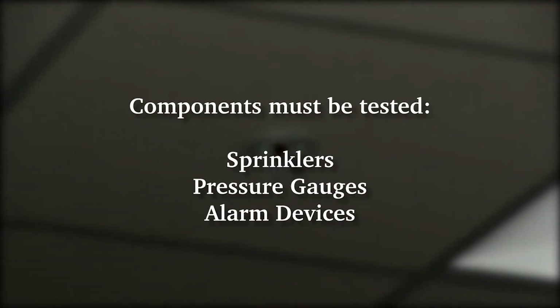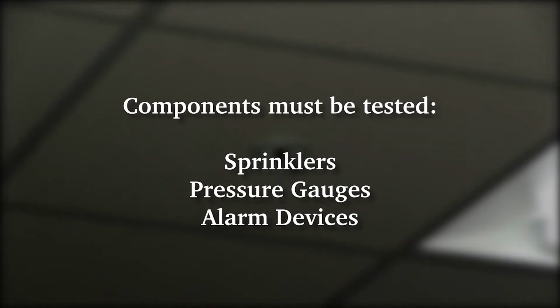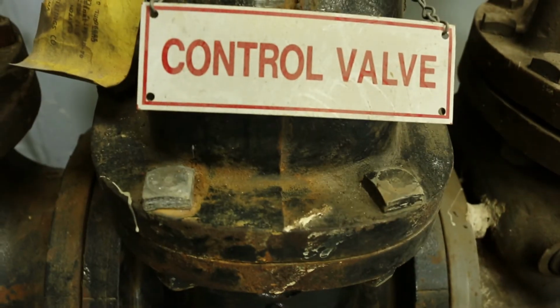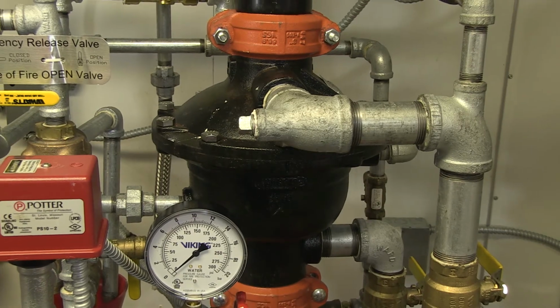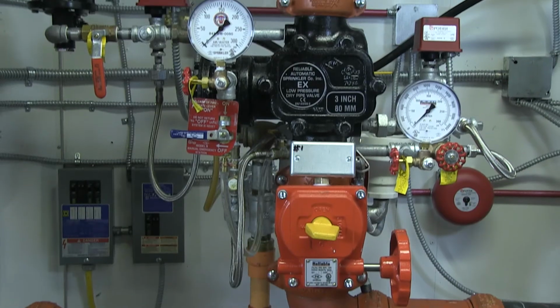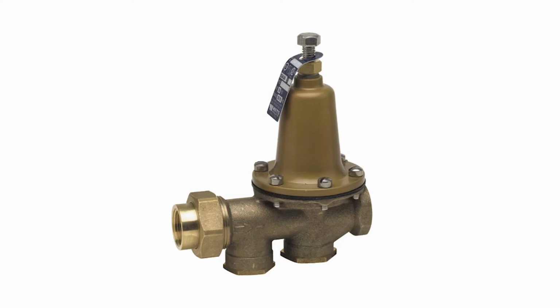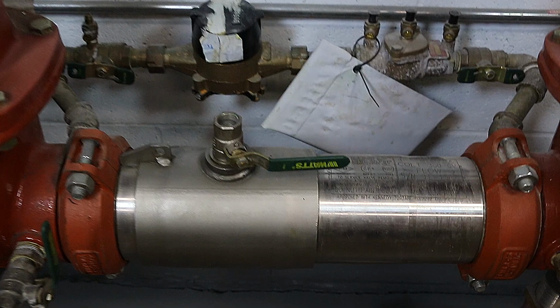Sprinklers, pressure gauges, and alarm devices are components that must be tested. Valves, valve components, and trim must be inspected, tested, and maintained. ITM must also be applied to water control valves, alarm and check valves, pre-action and deluge valves, dry valves, hose valves, pressure-reducing valves, and backflow prevention devices.